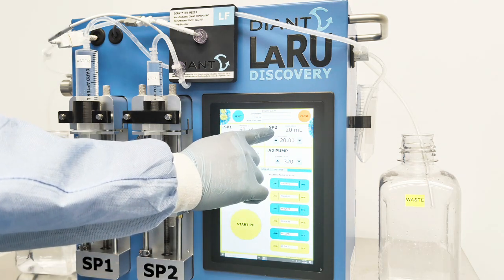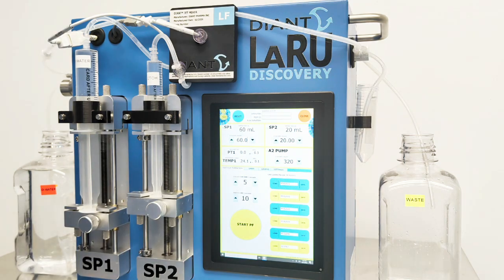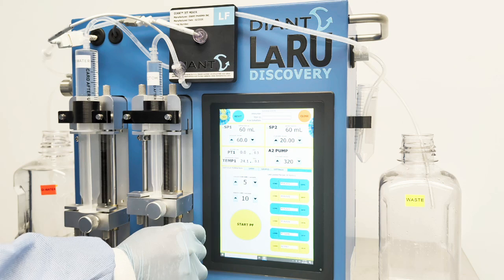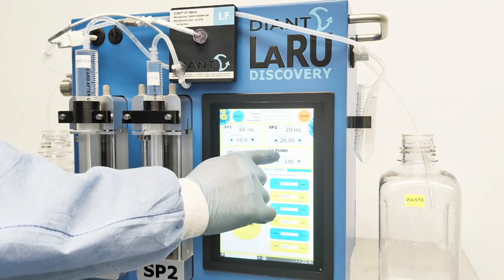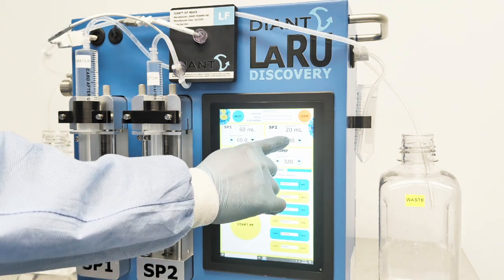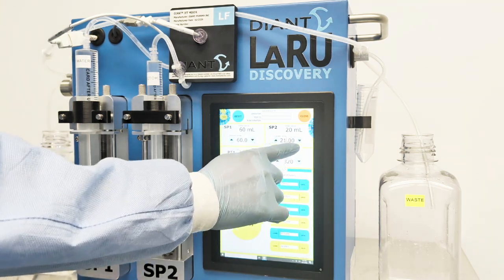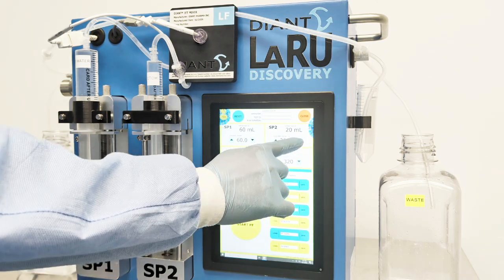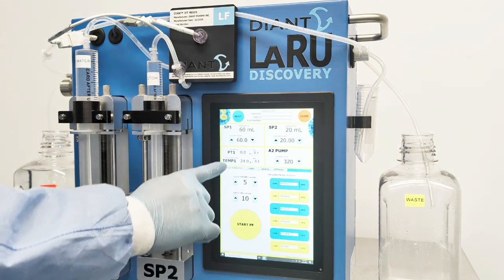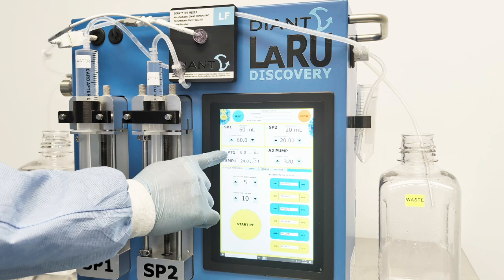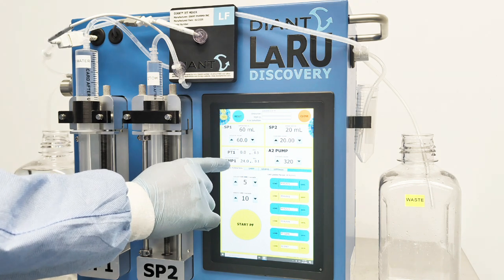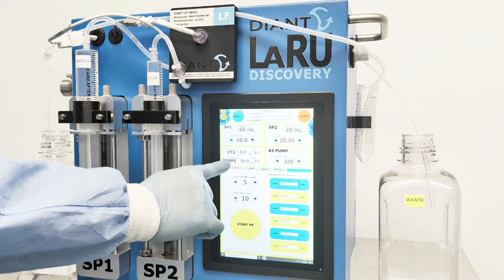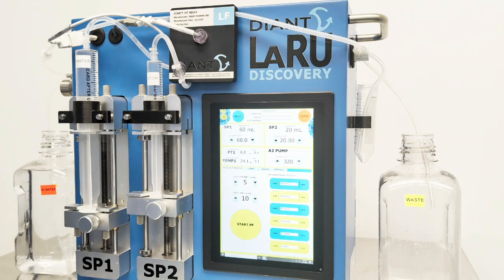SP2 pump has a similar setup where you have the LED on the left-hand side, which indicates proper connection and communication. And then you also have the syringe size, and then the syringe flow rate setting. There are two sensors on the system: PT1, which is a pressure transducer, and Temp1, which is a temperature sensor. PT1 is located downstream from the ethanol syringe, which gives us the pressure going into the DIANT jet mixer. The Temp1 sensor is located just downstream from the actual mixing site inside the DIANT jet mixer, and this gives you the particle formation mixing temperature.